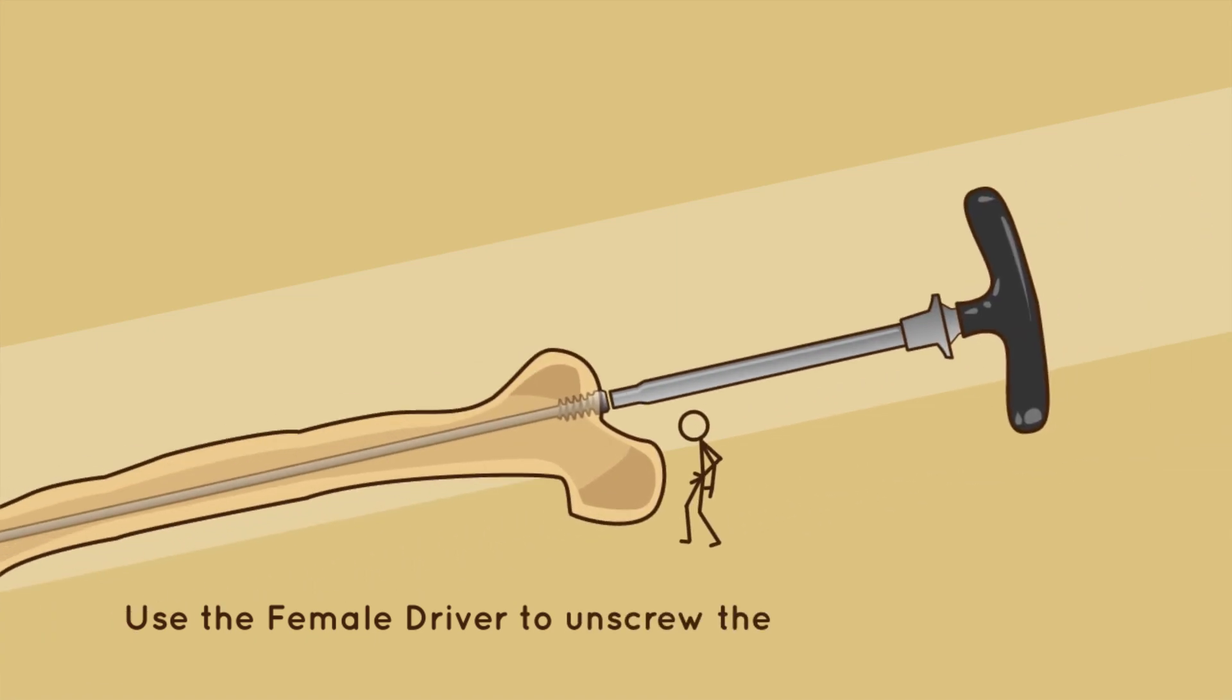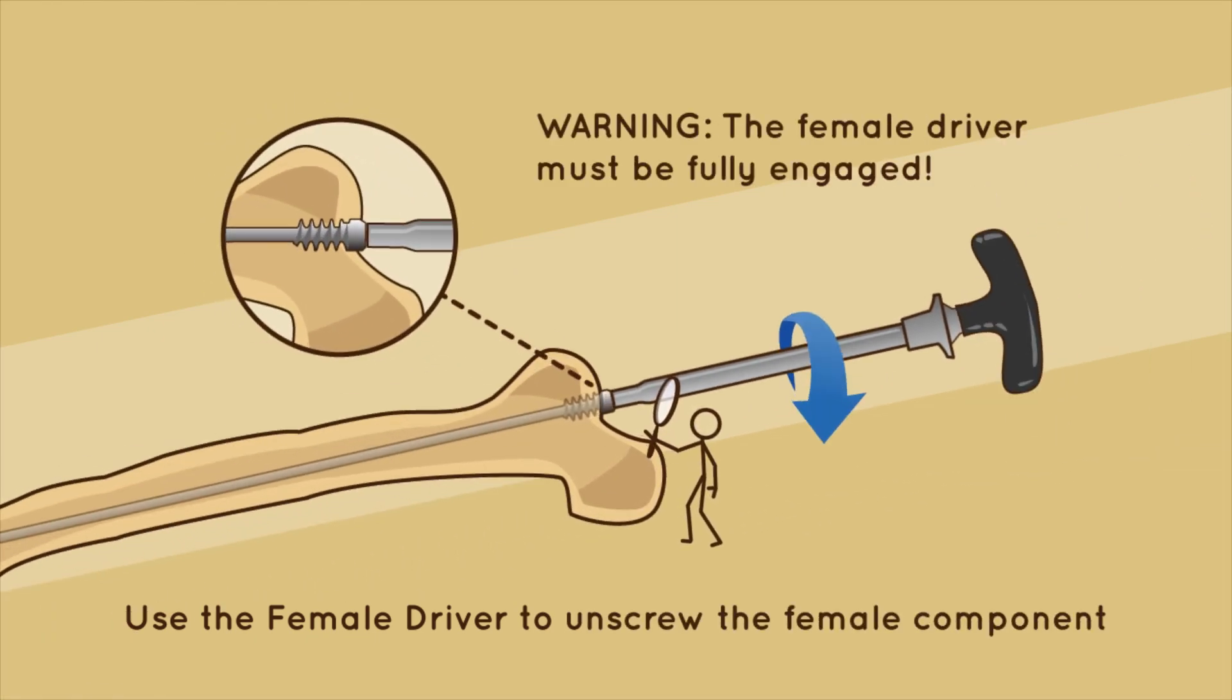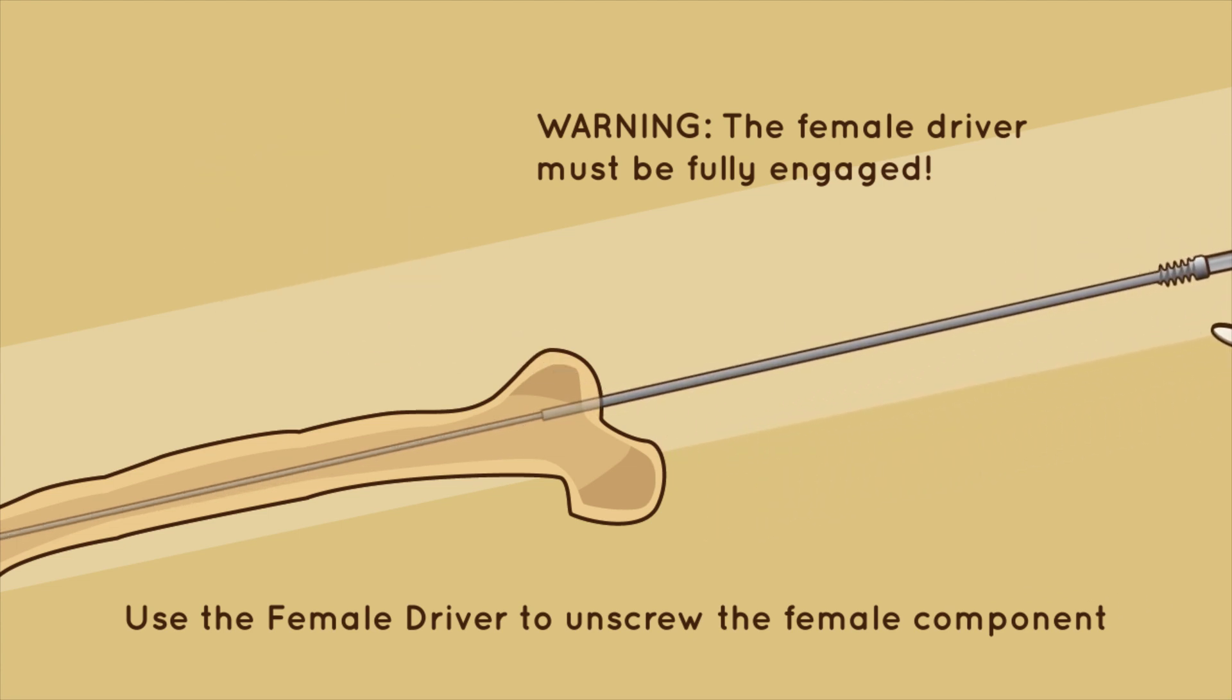Step 2. Use the female driver to unscrew the female component. The female driver must be fully engaged into the hexagonal drive of the implant.